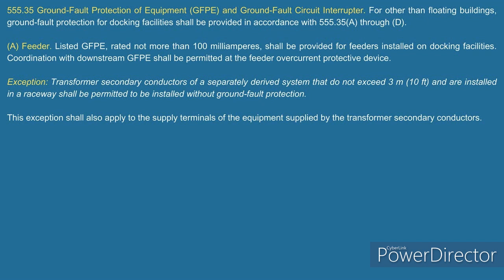So if I have luminaires on my dock, on my boatyard facility, I've got to have GFCI protection for those as well. If I have hardwired equipment, remember hardwired equipment terminates at an outlet where the hardwired equipment meets the premises wiring, that's the outlet. So it's not just GFCI protection for receptacles, it's GFCI protection for just about everything that's on that marina or boatyard. Oh yeah, everything, man. Just everything. Okay. GFCI everything.